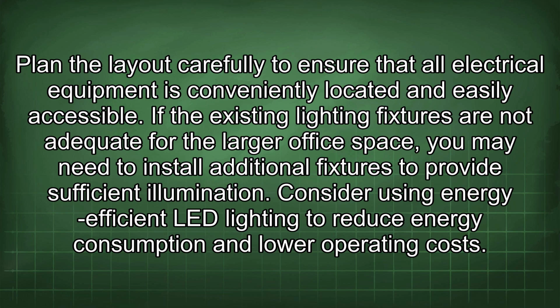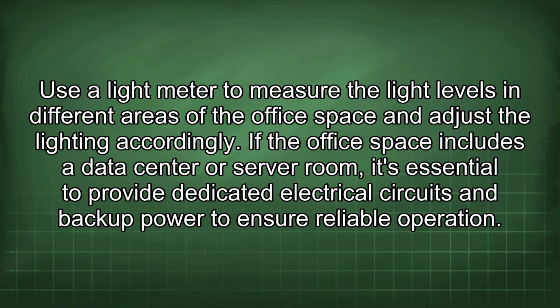If the existing lighting fixtures are not adequate for the larger office space, you may need to install additional fixtures to provide sufficient illumination. Consider using energy-efficient LED lighting to reduce energy consumption and lower operating costs. Use a light meter to measure the light levels in different areas of the office space and adjust the lighting accordingly.